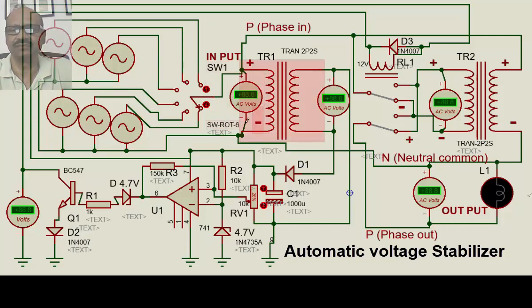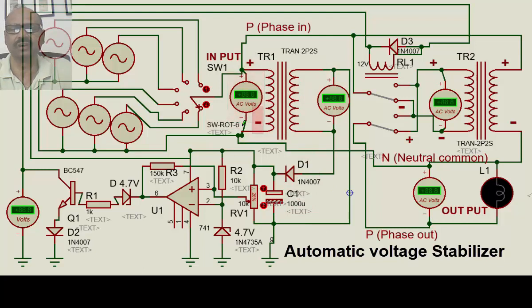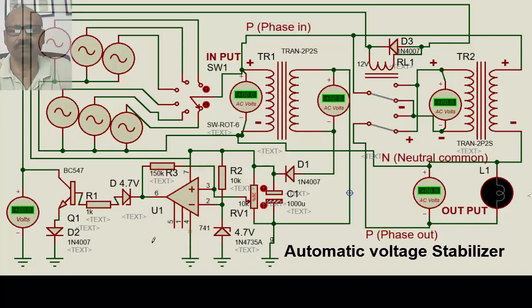We have a small transformer called a signal transformer, which is only for powering the electronic circuits. The primary is connected to the supply — 230 volts or whatever voltage is coming in — and the secondary is around 12 to 15 volts, which is then rectified and filtered into DC, and that DC is given to an operational amplifier used as a comparator.